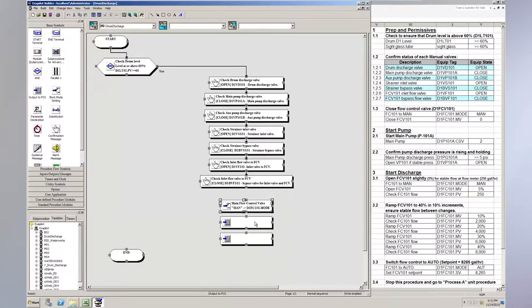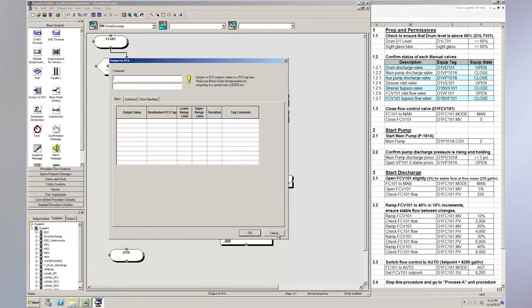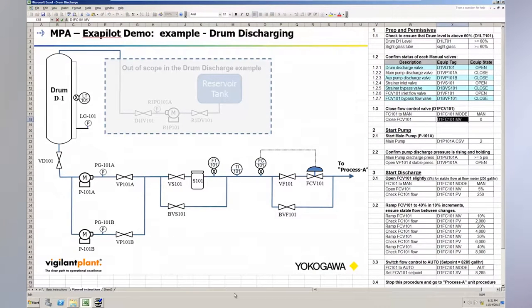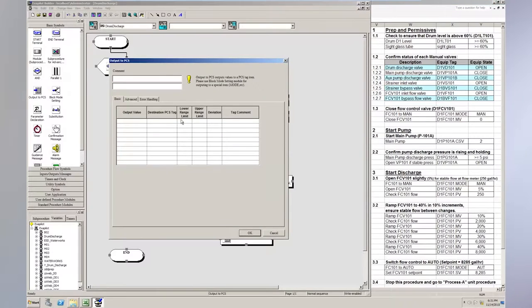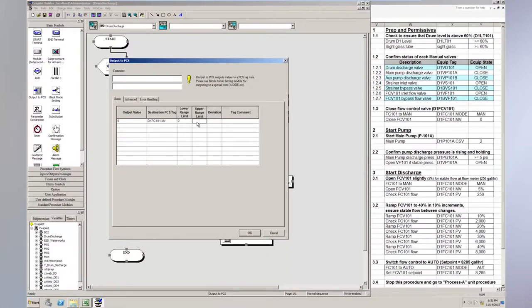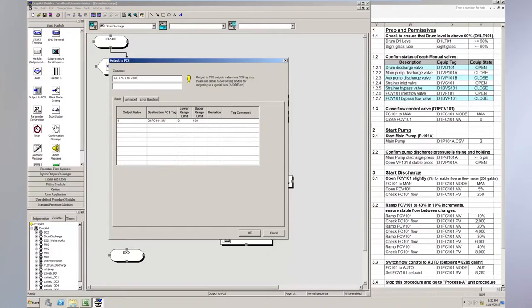And then I need to do the same thing. I need to set the flow control valve output to zero. So this is going to be the tag here, the MV with the manipulated variable. It might be .op on your control system. It depends on your control system. And the value is going to be zero. And I'll put the range in. And this is the flow control output. Output to flow control valve.